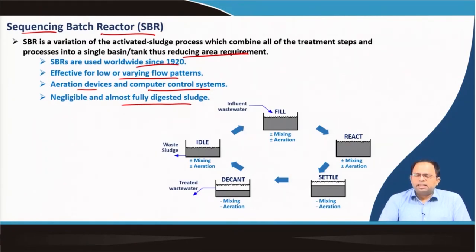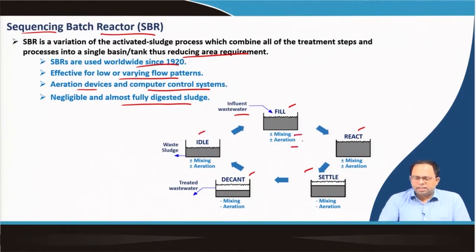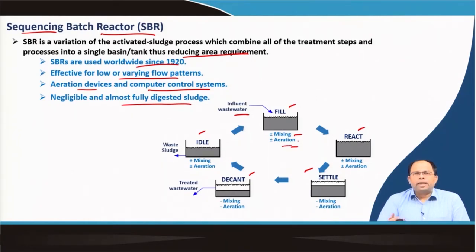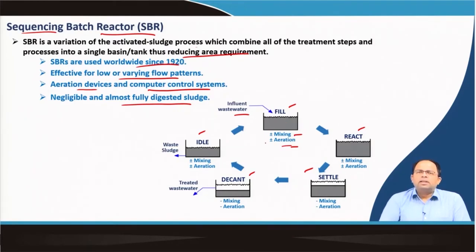In this image you can see the different stages or sequences. Incoming influent wastewater goes through: fill, then react, then settle, then decant, and then idle. The two basic processes are mixing and aeration — we mix the wastewater with the existing sludge which holds the bacteria, and aeration is the process of putting air into the chamber. In the activated sludge process we use both air and existing sludge to start the biological reactions.